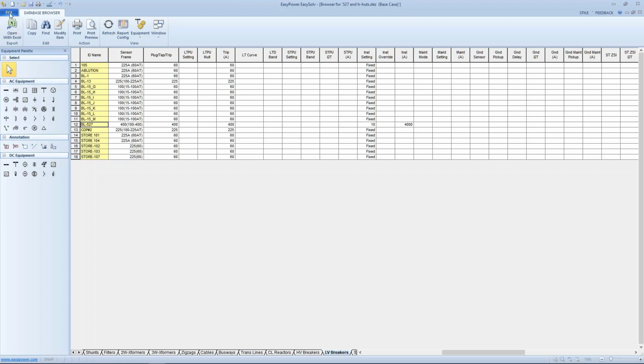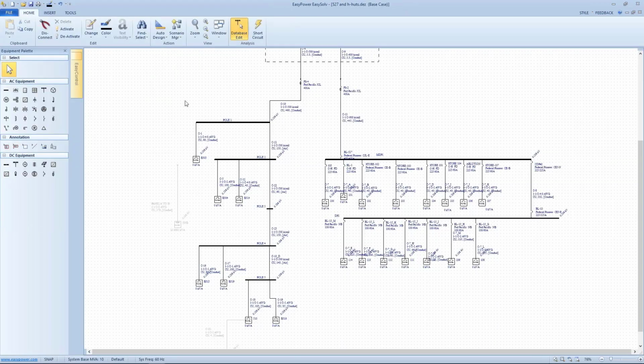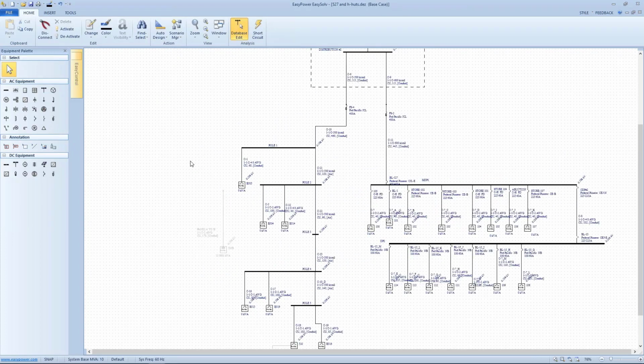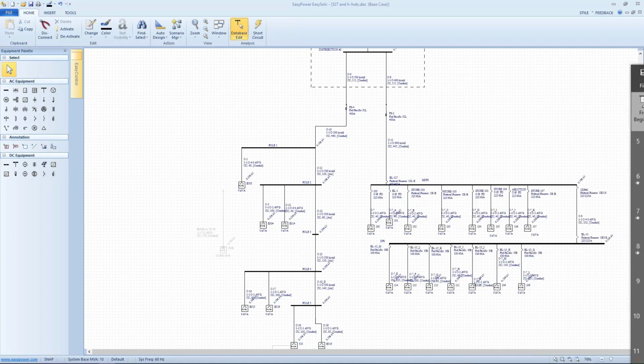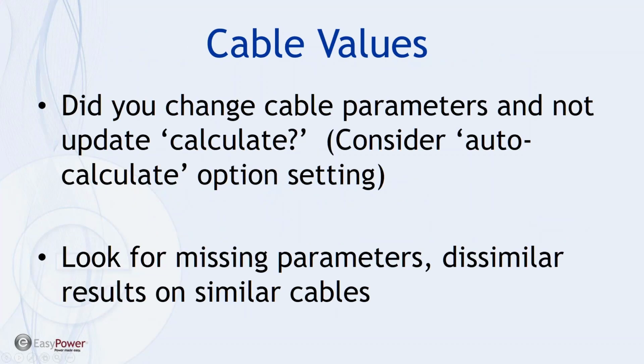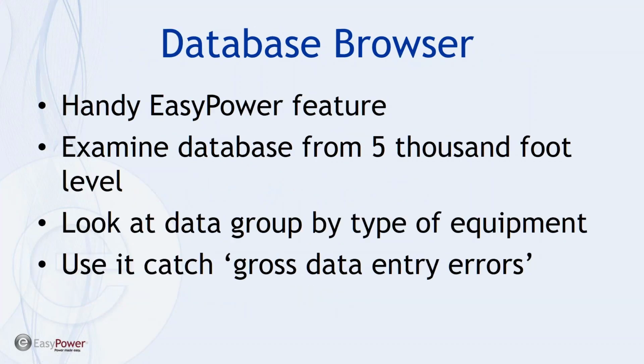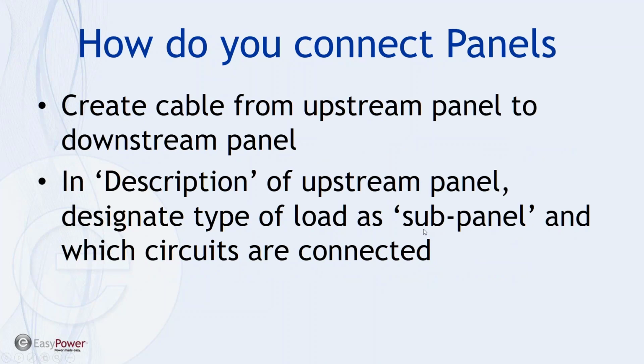This utility is called Database Browser, and it's extremely valuable in finding missing data and troubleshooting a problem. Now, we talked about the default settings. One other thing I would touch on goes back to my material. All right, so we talked about cable values. We talked about the database browser, and again, we're primarily looking for gross data entry errors and an indication that you're missing something, but it's not really clear whether it's a data entry problem or a problem with the data being collected. Okay, the next question that came up is how do I connect panels?